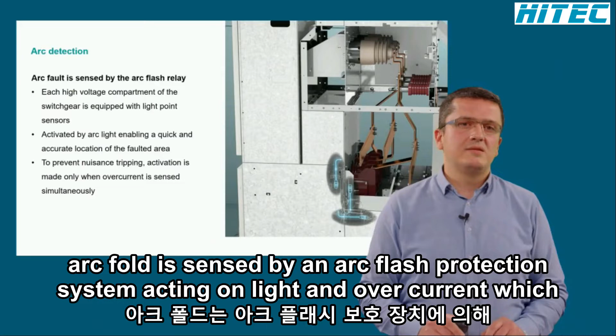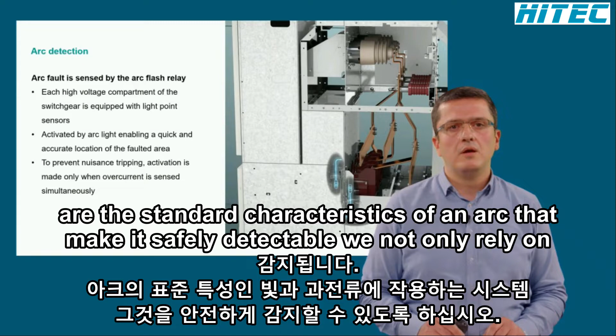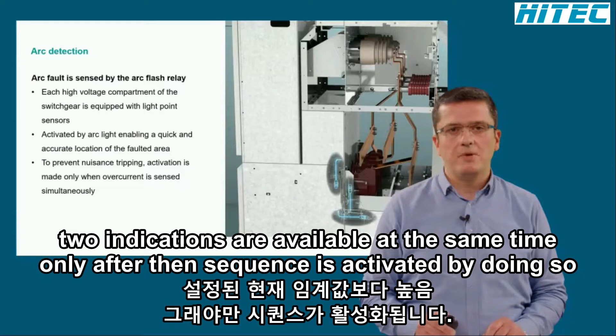Arc fault is sensed by an arc flash protection system acting on light and overcurrent, which are the standard characteristics of an arc that make it safely detectable. We not only rely on light, but await an overcurrent signal which is above the set current thresholds. When those two indications are available at the same time, only then is SIQuench activated. By doing so, nuisance activations due to external disturbances are avoided.